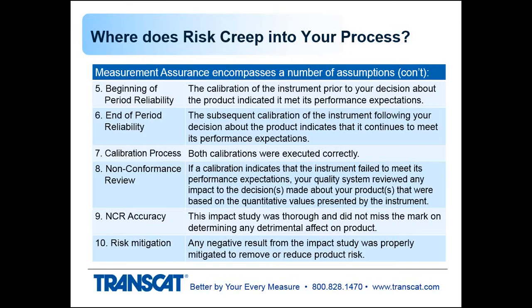Number 7 is the calibration process, and having good measurement assurance has to do with ensuring that the calibrations were executed correctly. The details of that could be that the tolerances of the calibration were set incorrectly, the procedure or methodology was wrong, or the number of test points, ranges or functions weren't covered. So number 7 assumes that the full calibration was provided for the unit that supports the use of the instrument in the application based on its suitability decision.